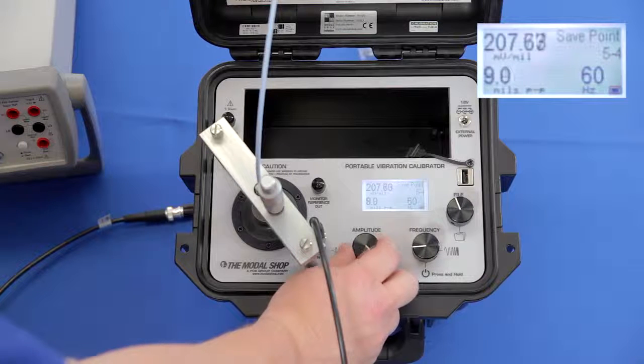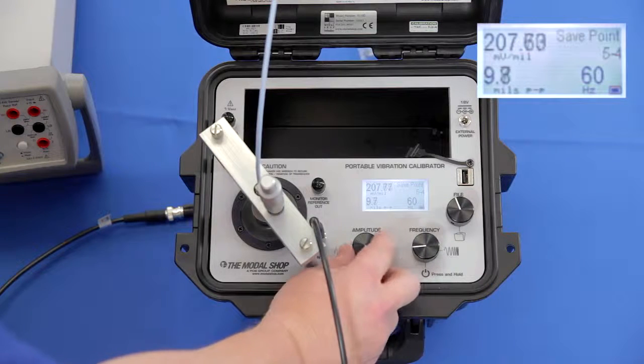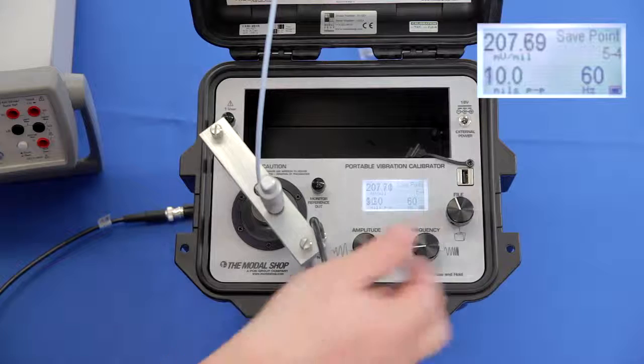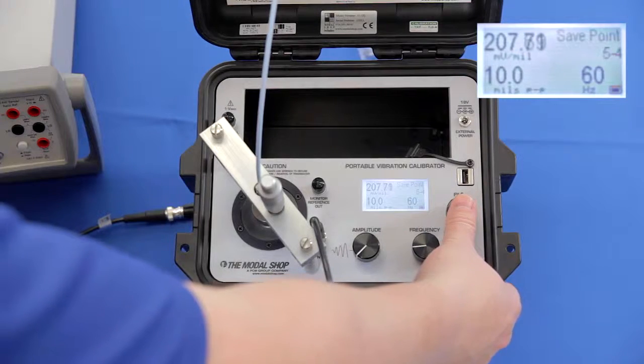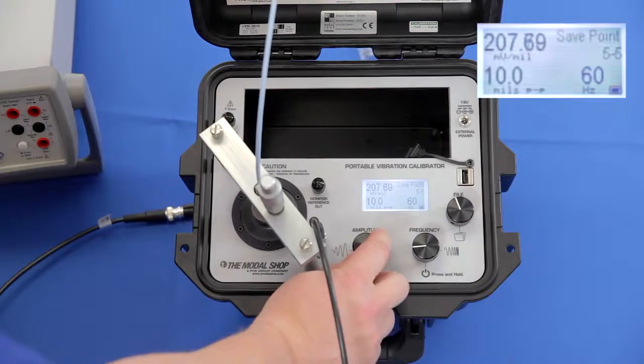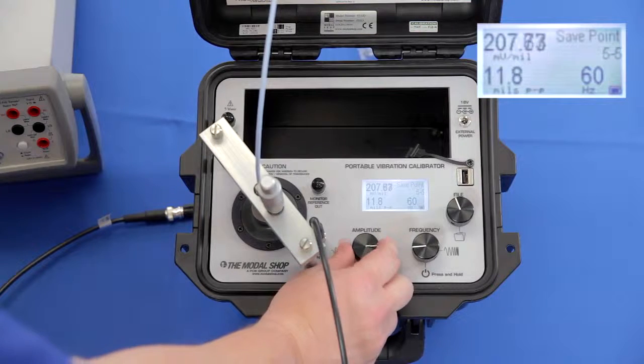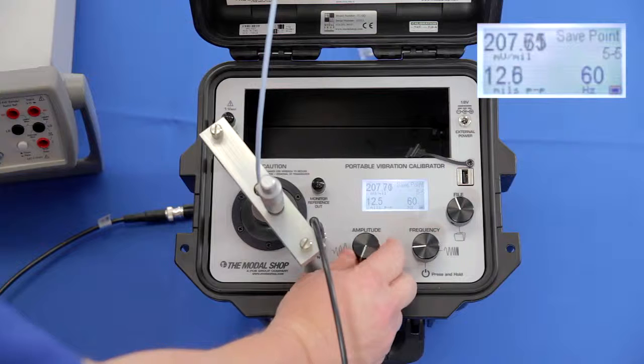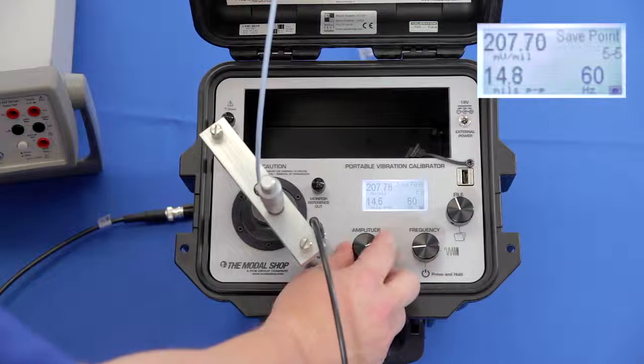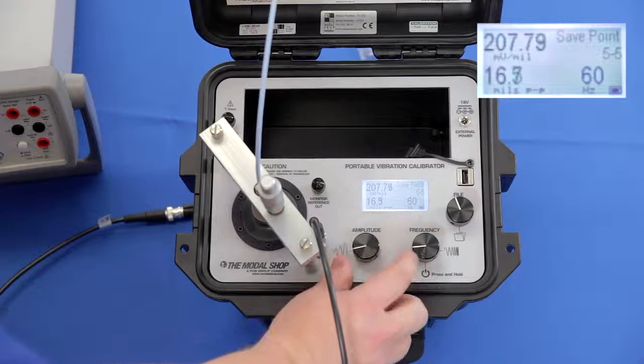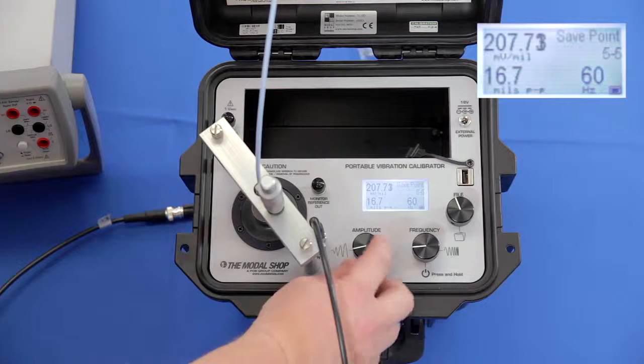So in the field for a plant floor or an in situ calibration at the machine site, you can actually check your alert and alarm levels. And notice as I change my amplitude in mils peak to peak, I don't have to remove the sensor and replace a micrometer. The shaker's controlling it and changing it for me. The shaker's making sure that I remain at 60 hertz so I don't have to change the frequency constantly.